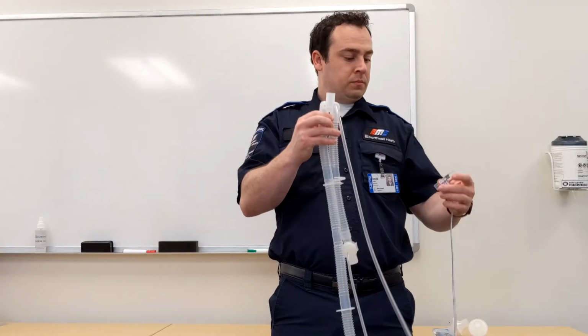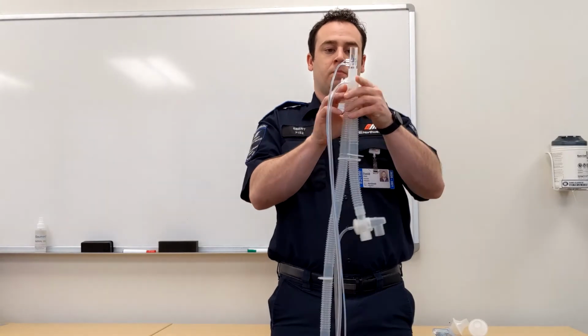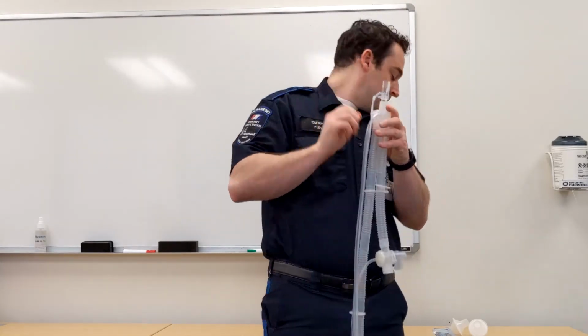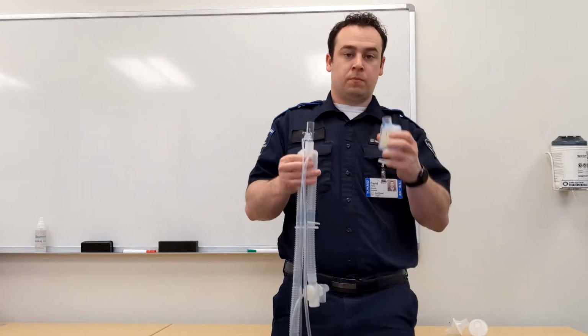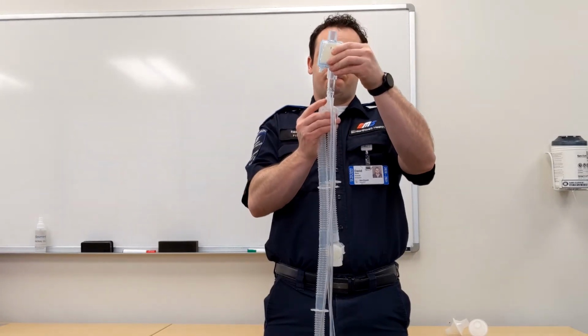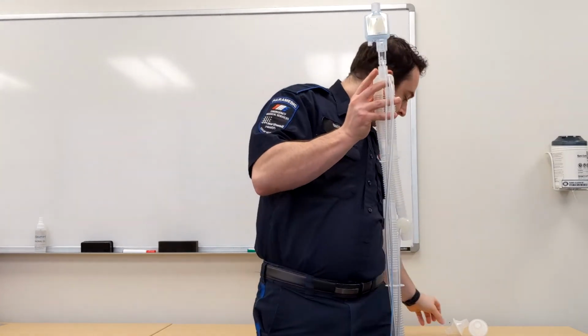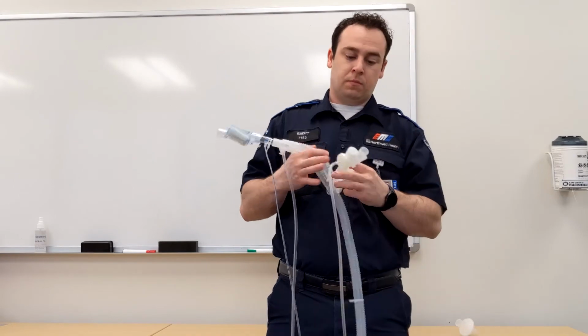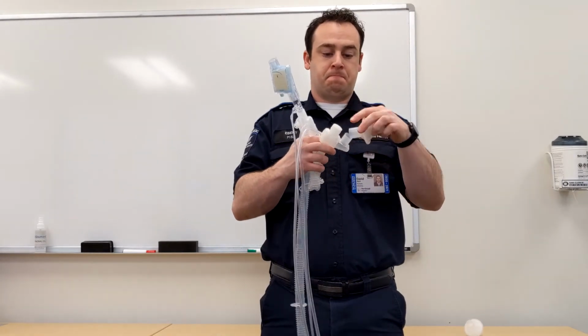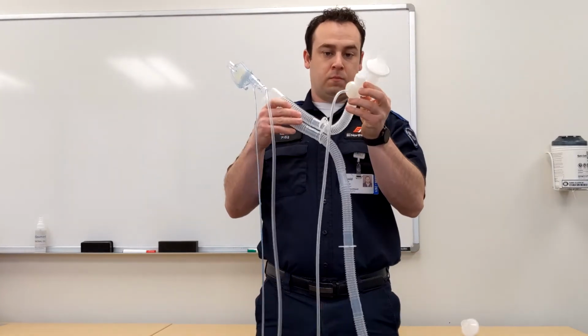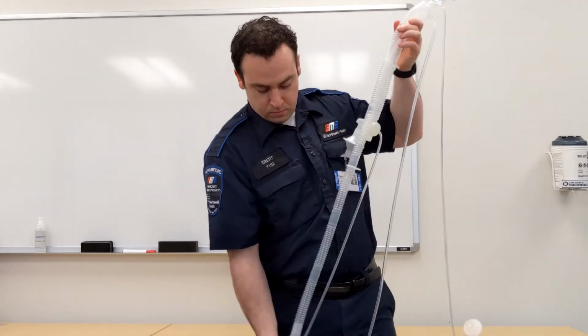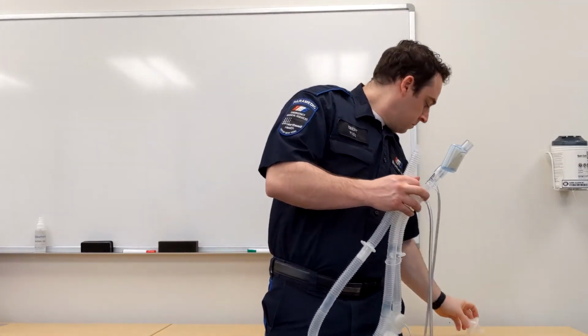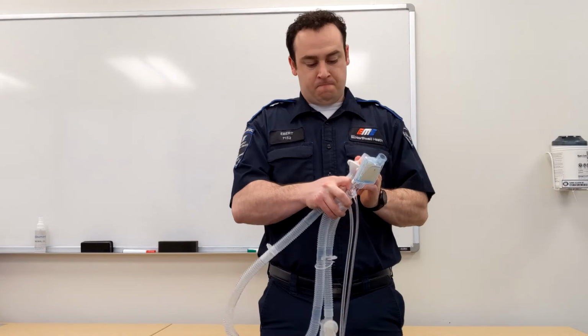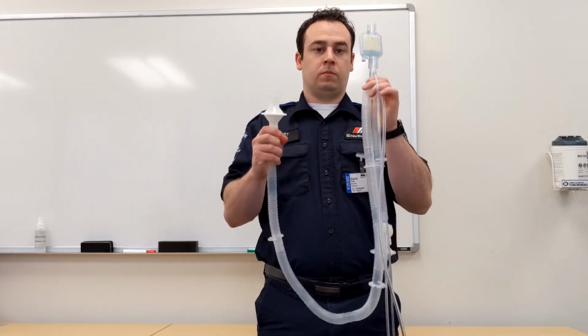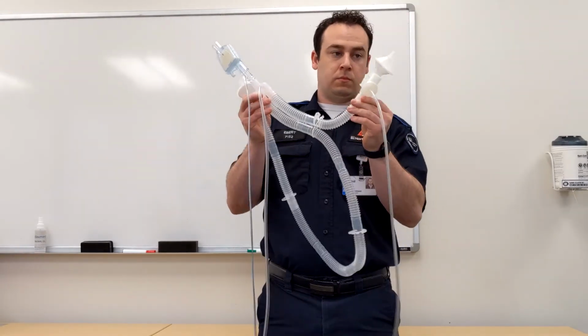When setting up your circuit, place the flow sensor on the Y piece end. Be sure that the flow sensor is facing up. Next, place the HME filter on top of the flow sensor. After this, place the inline filter at the end of the expiratory limb. Notice that we do not pull the exhalation valve off the circuit and place the filter in between the expiratory limb and the exhalation valve like we did with the HT70. Lastly, let's put the inline filter at the end of the inspiratory limb.